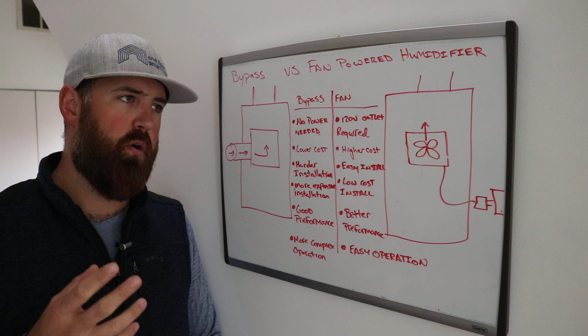Bypass humidifiers have a summer and winter setting for the bypass damper on the side of them. You've got to remember to set that, which is something people forget. So you'll see people with the bypass always open, even in the middle of summer, or closed in the winter, and then the humidifier isn't performing as expected. It's something you have to remember to do, and not everybody does.